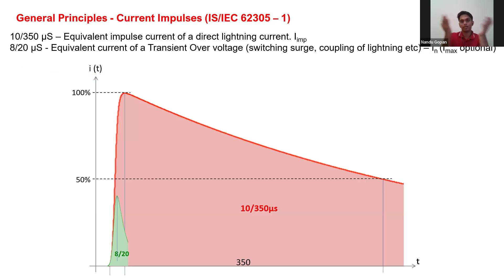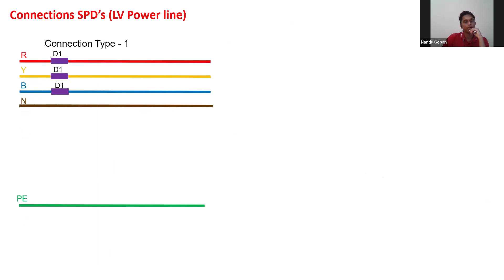So, connection type 1. There are two types of connections for SPD. This is type 1. So you have line conductors, L1, R Y B, and neutral, and PE conductor. This is connection type 1. This is called 4 plus 0. So 4 numbers of SPD between R Y B and neutral. So there will be live conductors and PE conductor, and there will be 4 numbers of SPD between them.